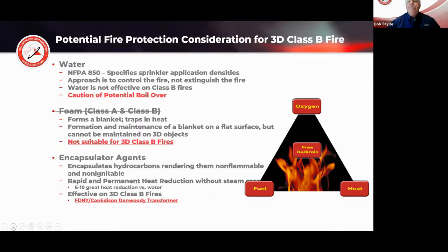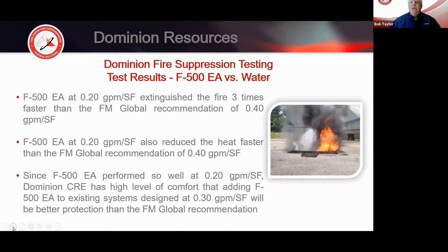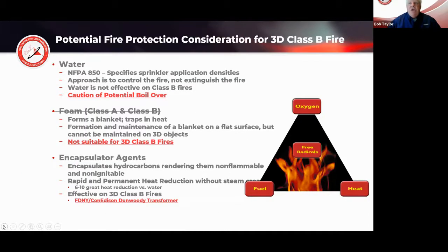Foams, both Class A and Class B foams, regardless, form a blanket trapping the heat, and they generally have to form and maintain a blanket on a flat surface, which is not realistic on a 3-dimensional fire. So they're really not suitable for a Class B fire. Encapsulating agents, again, encapsulate the hydrocarbons, the oils and so forth, rendering them non-flammable, non-ignitable. They have a very rapid and permanent heat reduction without steam, about 6 to 10 times greater heat reduction than water. And again, effective on 3D Class B fires.